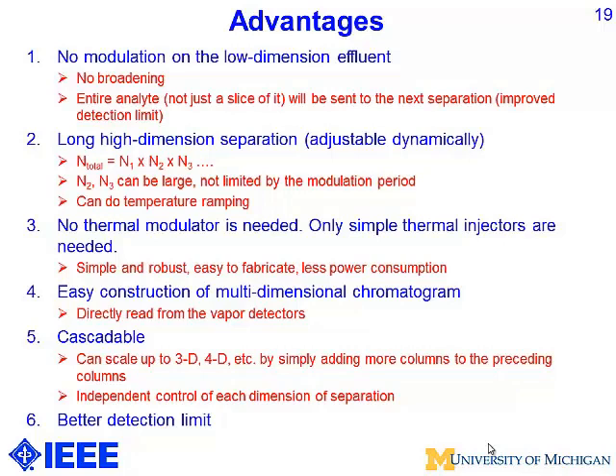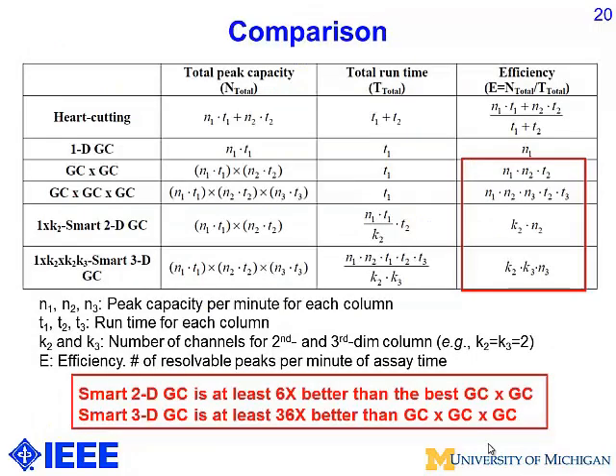Smart 2D GC also has a better detection limit because instead of cutting peaks into small slices, we send entire peaks into second or third dimensional columns. Comparing our approach to traditional GC×GC and GC×GC×GC: smart 2D GC is at least six times better in peak capacity than the best GC×GC, and smart 3D GC is at least 36 times better than GC×GC×GC. Comparing smart 3D GC with current existing 2D GC, we are probably at least 100 times better.